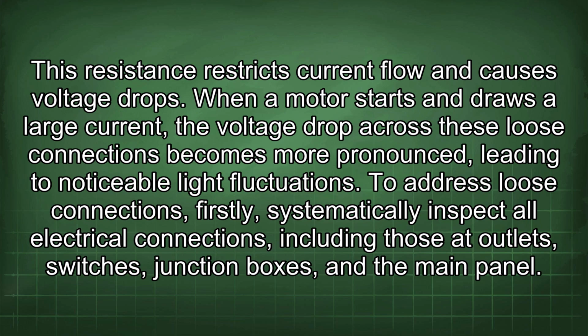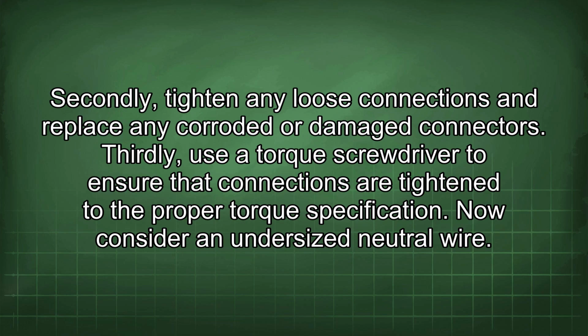to noticeable light fluctuations. To address loose connections, firstly, systematically inspect all electrical connections, including those at outlets, switches, junction boxes, and the main panel. Secondly, tighten any loose connections and replace any corroded or damaged connectors. Thirdly, use a torque screwdriver to ensure that connections are tightened to the proper torque specification. Now consider an undersized neutral wire.